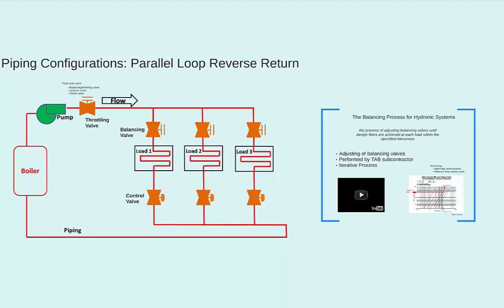Well, if you don't have a properly balanced system, the chance of being able to control it properly is slim to none. The balancing process is done with the control valves wide open. This ensures that on the coldest day of the year, the control valve can fully open and the correct amount of flow will be provided. All other times of the year, the control valve will be positioned somewhere less than fully open, depending on the heating requirements of the building.